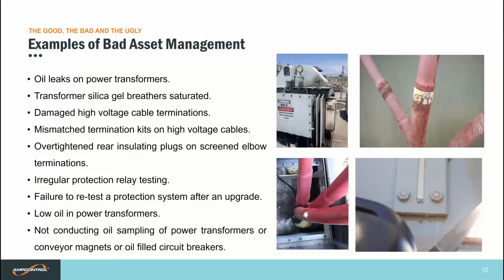Back onto the screen, we have some examples of bad asset management. Running through the list: oil leaks on power transformers, again, an environmental issue. Transformer silica gel breathers saturated, so when the colour changes, it means it's not doing its job. Damaged high voltage cable terminations, mismatched termination kits on high voltage cables, over-tightened rear insulating plugs on screened elbow terminations, which is one of our case studies today, irregular protection relay testing, failure to test the protection system after an upgrade, low oil level in power transformers, or not conducting oil sampling of power transformers or conveyor magnets or oil-filled circuit breakers.